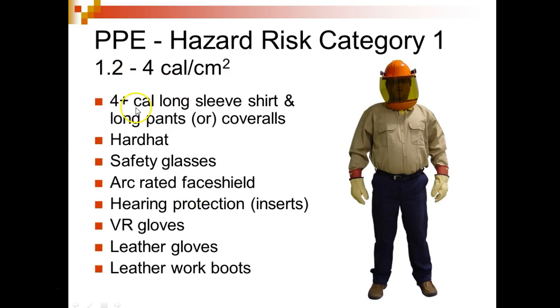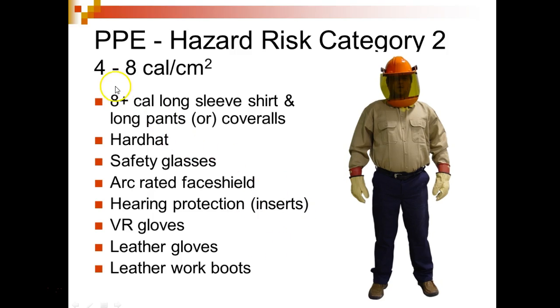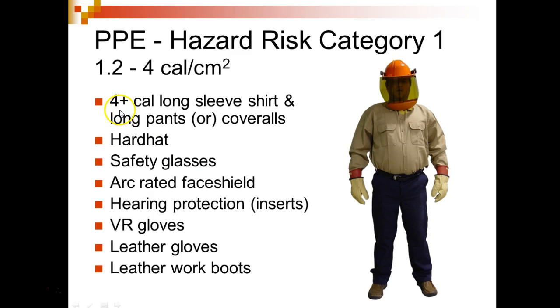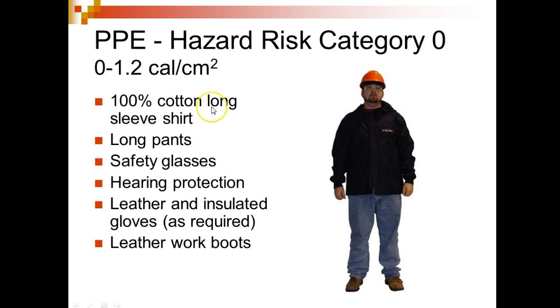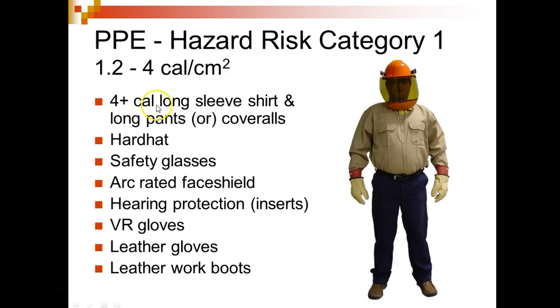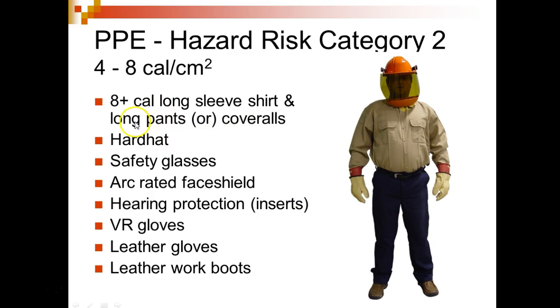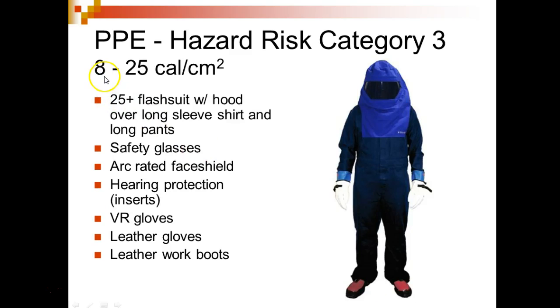But when you get into 1.2 to 4 calories, then you start getting into arc rated face shields, hearing protection, voltage rated gloves, leather gloves. So you're supposed to have rubber gloves under your leather gloves. Can you see that right there? And leather work boots. Then you get into this one. Here you wear a cotton long sleeve shirt. Here you wear calorie rated long sleeve pants and coveralls. Okay. It looks the same, but now your sleeves have to be rated 8+. That makes sense? And then we get into 8 to 25.